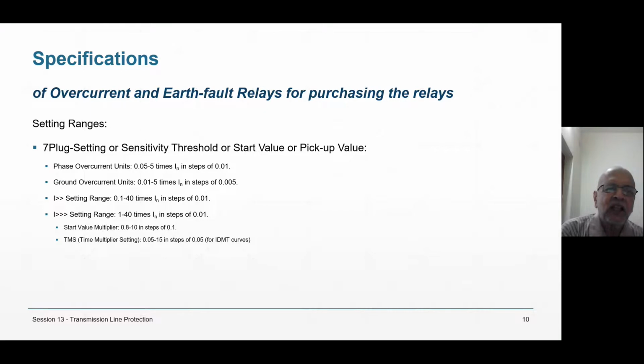Setting ranges. Plug setting, sensitivity threshold, or start value or pickup value. Phase overcurrent relays 0.05 to 5. You see, we were talking 50% to 200%. This is 0.05 to 5 times, and that too in steps of 0.01. If I start speaking each value now, I'll finish tomorrow morning: 0.05, 0.06, 0.07, 0.08, 0.09, up to 5. It will be morning tomorrow. Ground overcurrent relays 0.01 to 5 times IN in steps of 0.005.